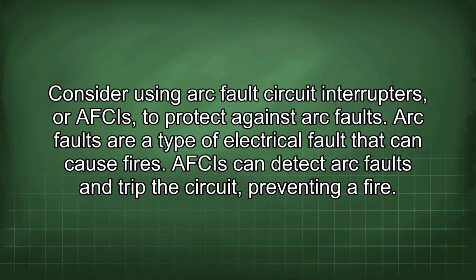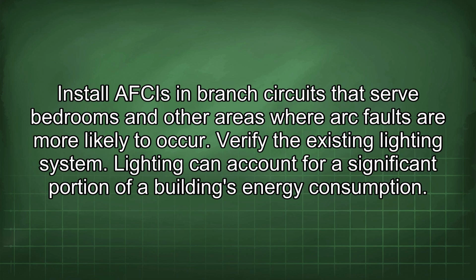Consider using arc fault circuit interrupters, or AFCIs, to protect against arc faults. Arc faults are a type of electrical fault that can cause fires. AFCIs can detect arc faults and trip the circuit, preventing a fire. Install AFCIs in branch circuits that serve bedrooms and other areas where arc faults are more likely to occur.